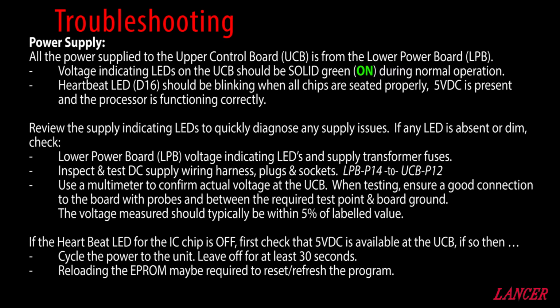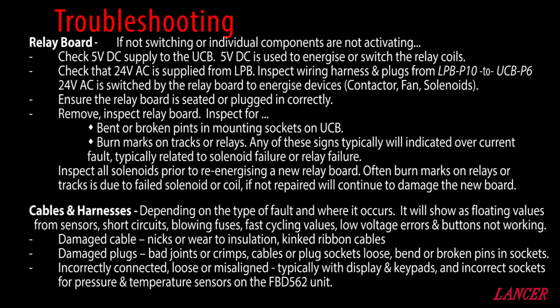If the heartbeat LED for the IC chip is off, first check that the 5V DC is available at the upper control board. If so, then cycle the power to the unit, leaving it off for at least 30 seconds, and then reloading the EEPROM may be required to reset and refresh the program. If the relay board is not switching or individual items are not activating, first of all, check the 5V DC supply to the upper control board.